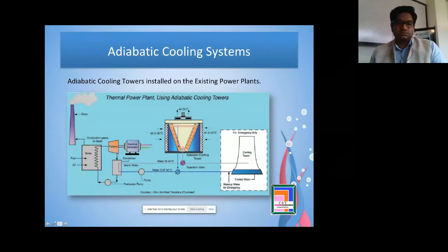So here I have shown how we can install an adiabatic cooling tower in an existing power plant. See, this is an existing power plant which has already been explained. So what we do is we tap two lines from here, and this is a three-way valve, and we close the cooling tower, and we install an adiabatic cooling system here. So the benefit is that this cooling tower works as an emergency if there is any problem in the system, or it acts as a reservoir for the makeup water for the 20% water of the adiabatic system.